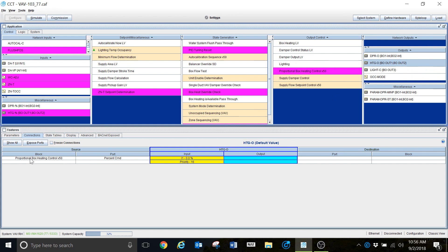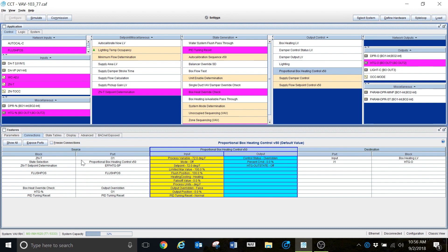I'm simply going to click this, and you can see on the output all of the connections. I'm following this logic back — you can see the Proportional Box Heating Control block, and the port is Percent Command. This is the actual output here; this is the input to this particular block and this is what is controlling it. So we're going to look now inside this Proportional Box Heating Control. When I click on it, you're going to notice this panel down here change. Here is all of the connections to this particular logic block — zone temperature going into the process variable.